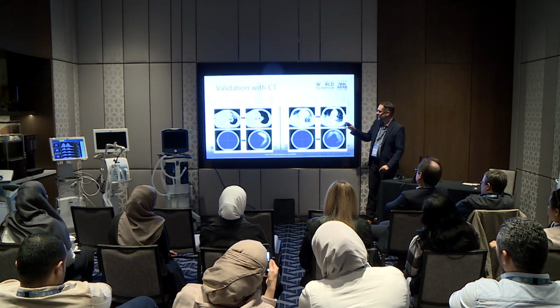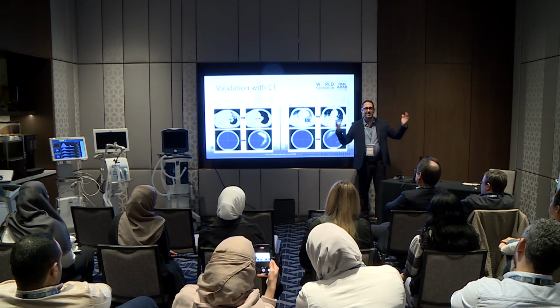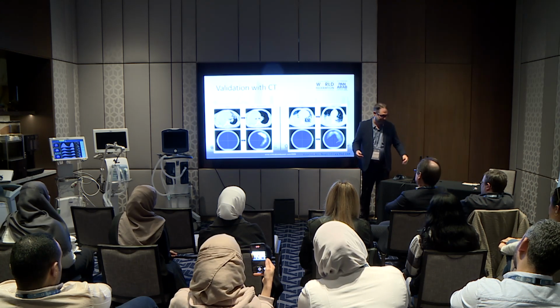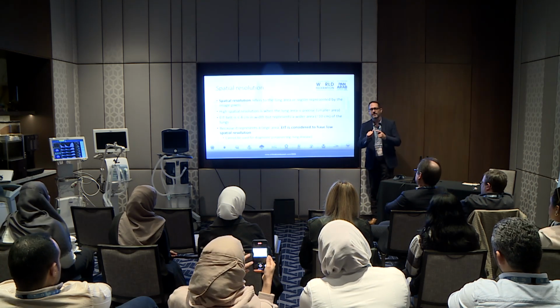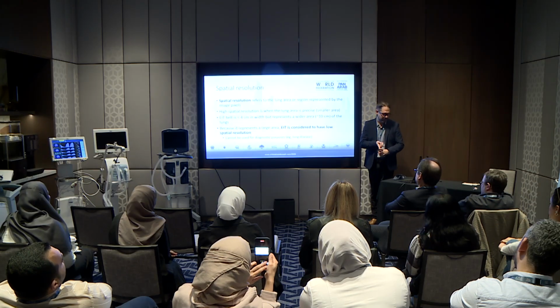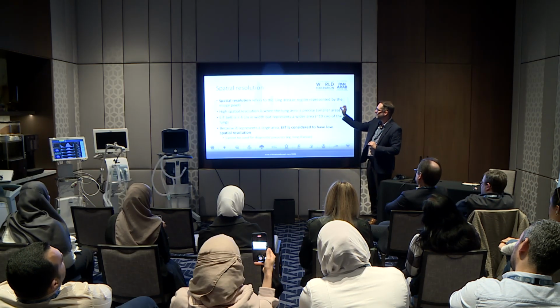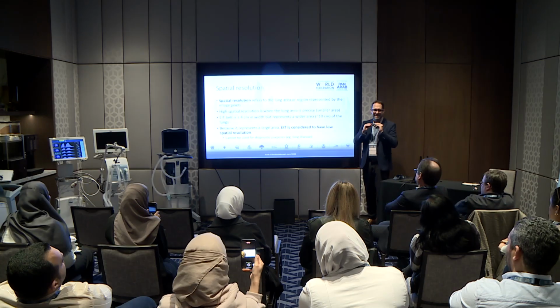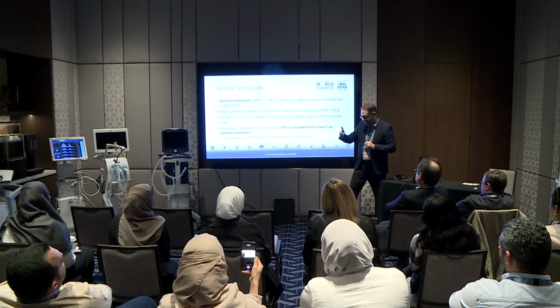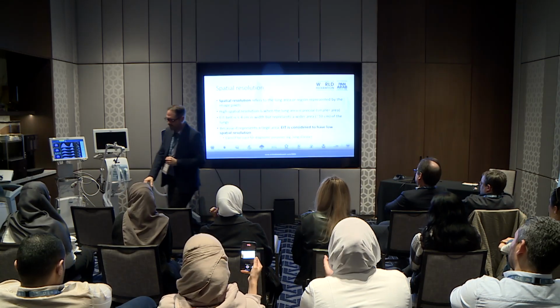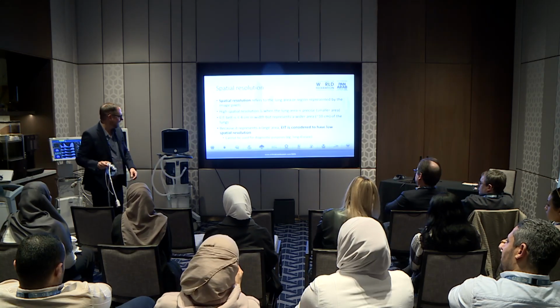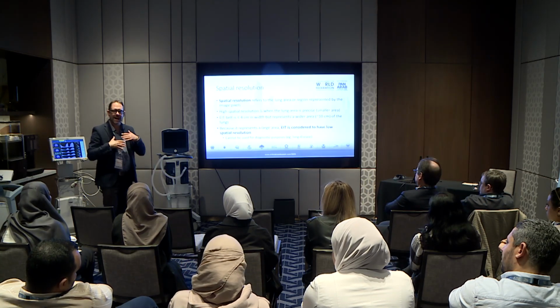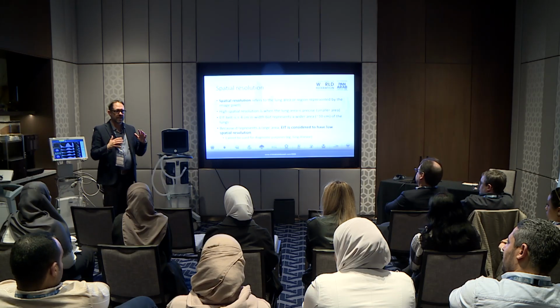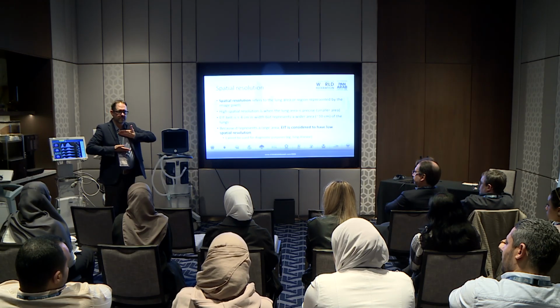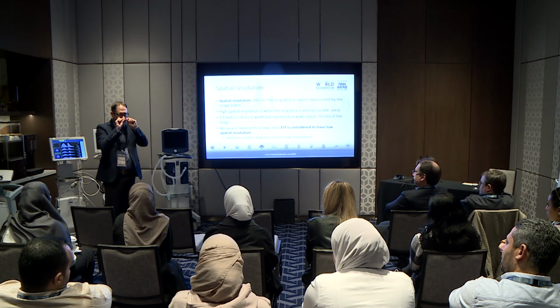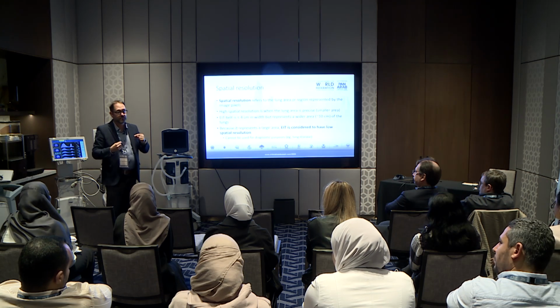But I want to point out the differences, like can we use it, do we never have to do a CT scan again, or should we never do ultrasound? And this comes down to things that are called spatial resolution and temporal resolution. So spatial resolution refers to the lung area or region represented by the image pixels. The belt, I showed you the belt, it's about 4 centimeters in width, okay? And what it captures in terms of the impedance changes is about 10 centimeters, okay? So it's not a very precise, specific area. If it was, we'd have to move the belt.